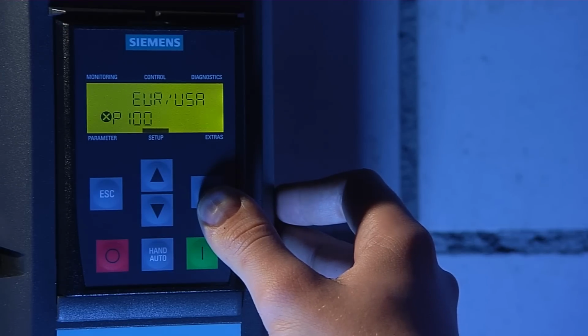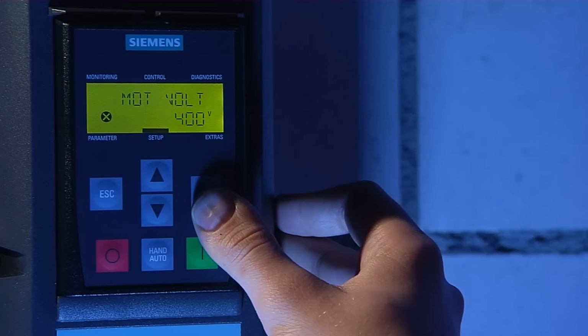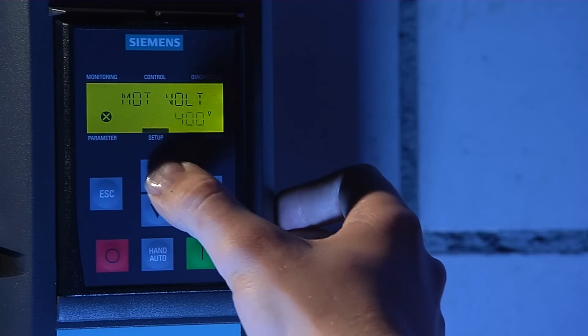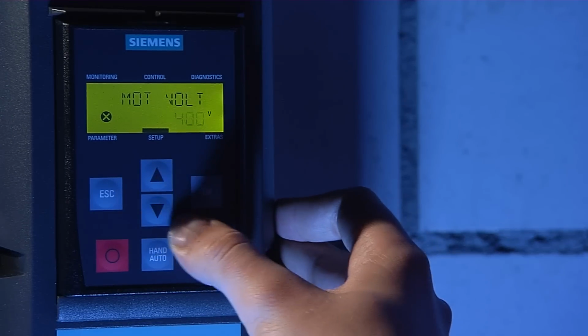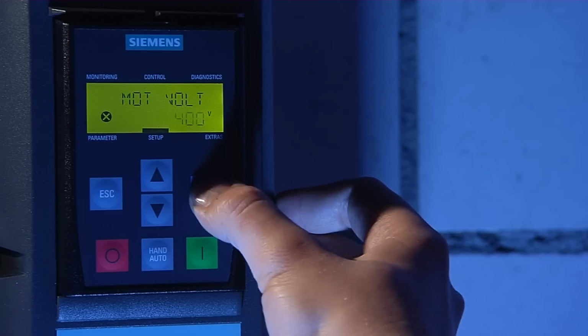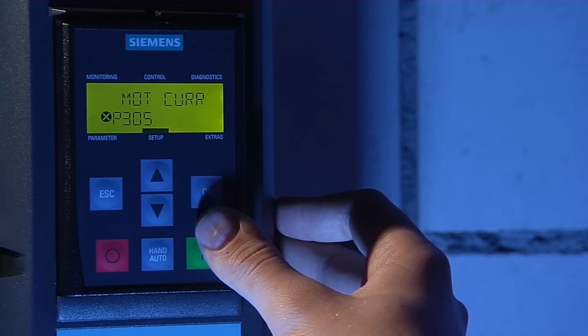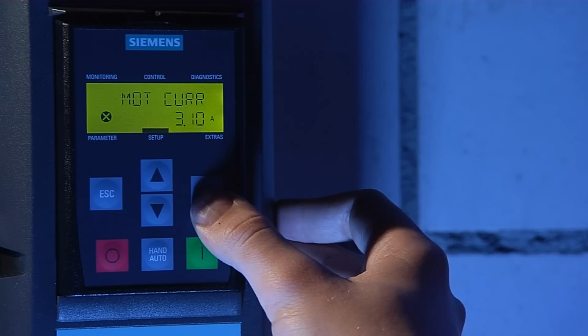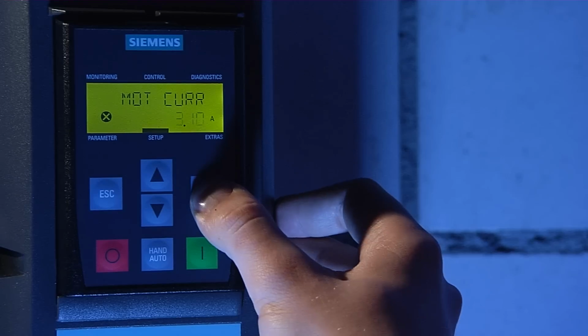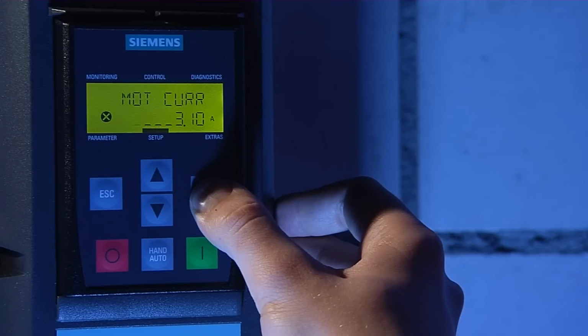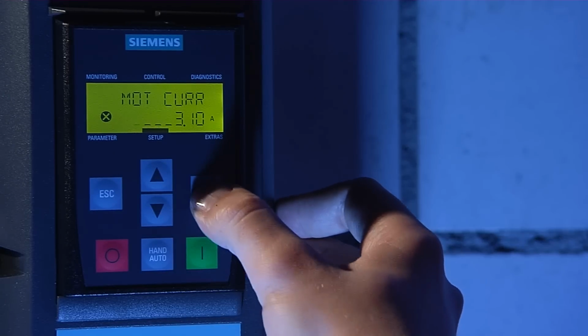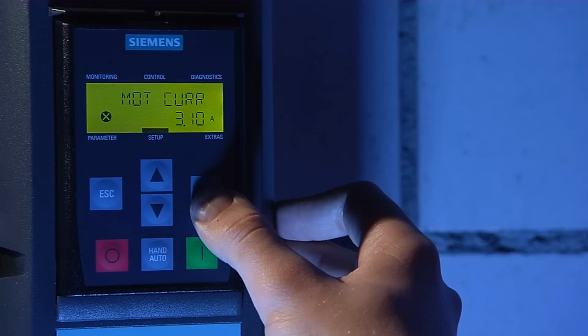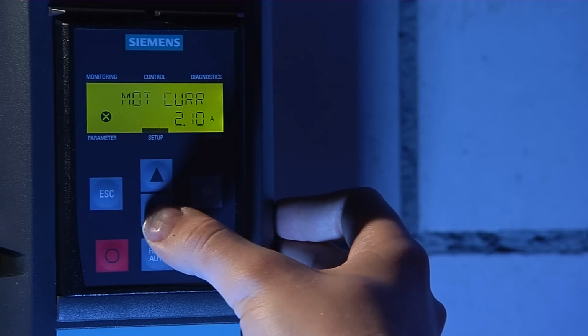In the next step, select the motor voltage. In order to quickly change the values, press and hold the up or down button. To prevent overshooting the target, you can change the value one digit at a time by holding the OK button down for 3 seconds. You can then use the OK button to select the required digit, and use the up or down buttons to change the value.